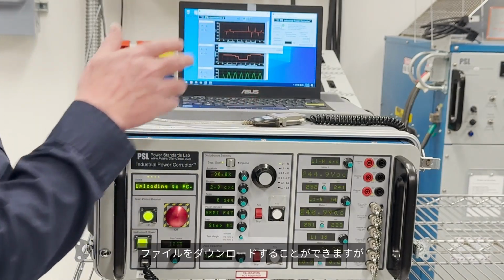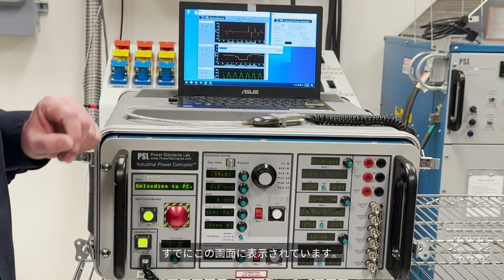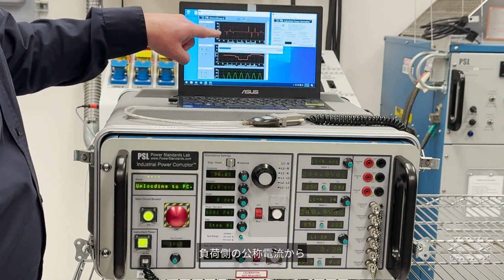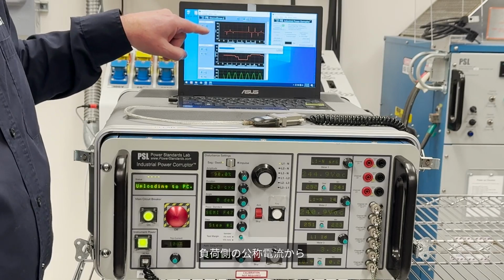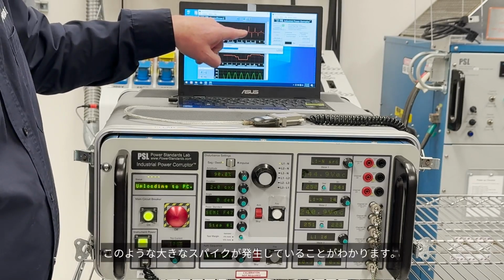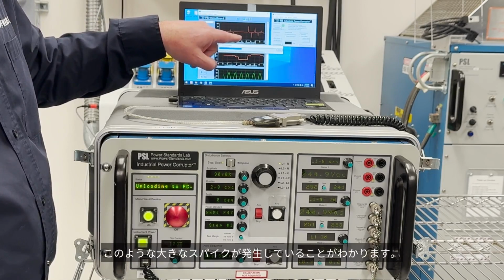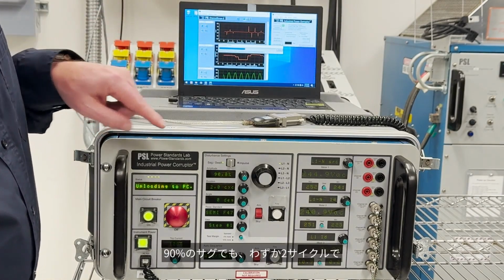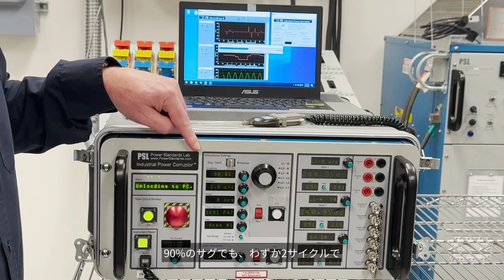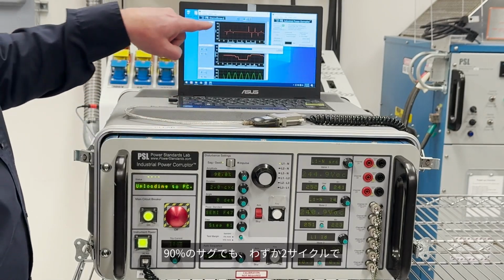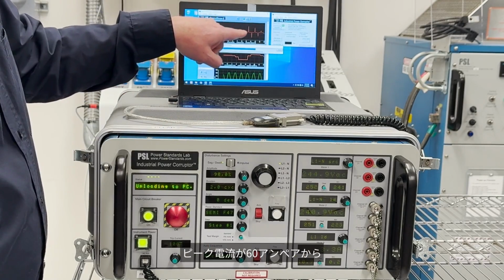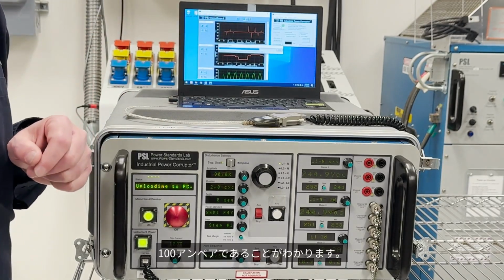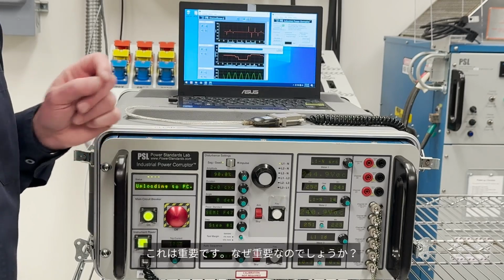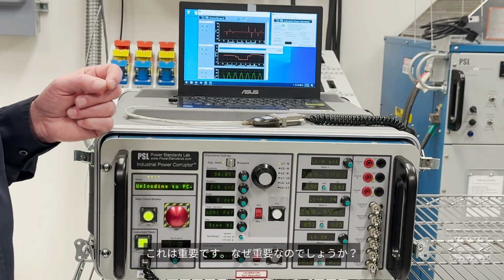We can download the file, but already I've pulled up on the screen here that going from a nominal current on the load side, we can see these significant spikes that occur even with a 90% sag for only 2 cycles. We can see that the peak current here is somewhere between 60 and 100 amps. Now that's significant. Why is it significant?